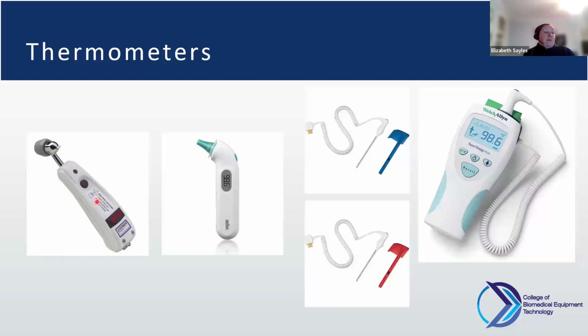The only other thing that we would do in biomed is the battery, which is a 9-volt battery, behind a little door that is screwed shut, I should say. Some clinicians get really handy and decide to replace the battery themselves, and they keep a flathead screwdriver handy. But biomed can go around and make replacements of those 9-volt batteries as well. There's no calibration of these devices specifically. Exergen is the main temporal scanner on the market, and so you'll see these primarily. There's no calibration of them.